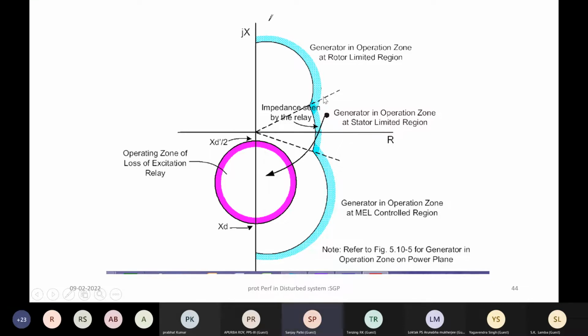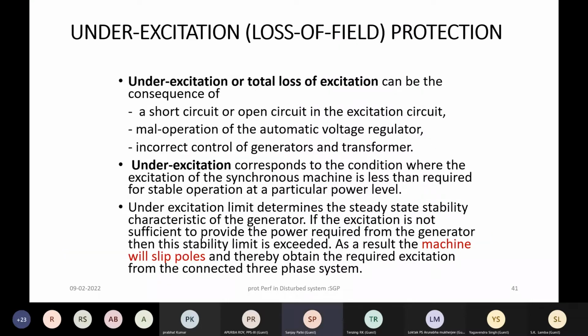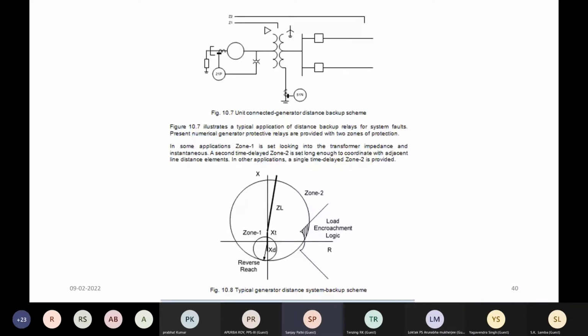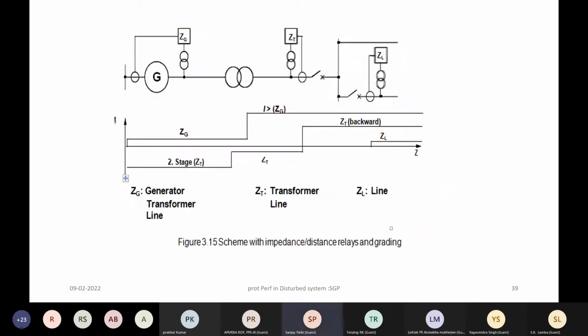So these are the various coordination methods by which one should ensure that there is no undesirable tripping, even if you operate the machine in under-excited mode. We talked about voltage support responsibility of the generator, especially when the voltage levels are high. If all the generators absorb the reactive power generated by the transmission network, then the over voltages can be controlled. And while doing that, if these protections are well coordinated, there won't be any undesirable operation. So this is related to coordination between under-excited relay and the capability curve. We talked about backup impedance relay and its reach.